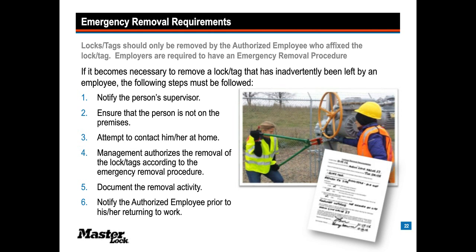And so often notification is made by posting signage at the machine where locks are removed, by posting notification at the entry point where the worker is expected to come in, by posting notification at a locker or at the time clock, and basically saying, don't go back to work until you've checked with your supervisor, your lock has been removed.